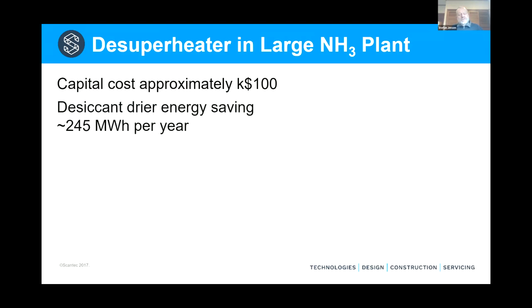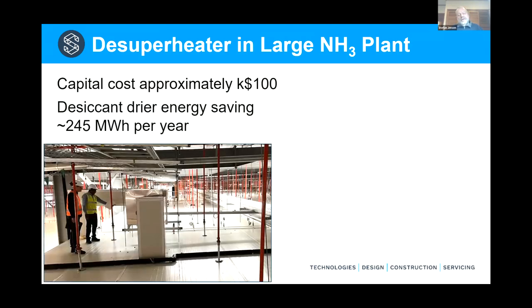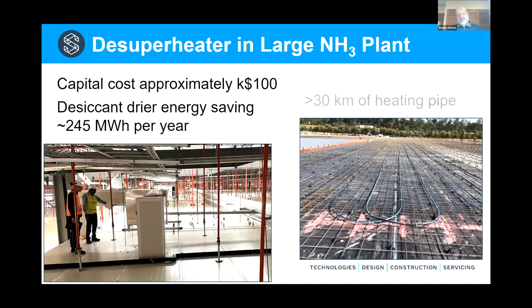So the capital cost of this system I showed you on the other picture is about 100,000. That does not include the storage tank. The insulated 316 stainless steel storage tank for the hot water will add another $70,000. So we are saving 245 megawatt hours a year. If that client pays 10 bucks or 100 bucks per megawatt hour, you can work out it's about $25,000 a year. So a payback of about 4 years. On the picture on the right, you see the subfloor heating pipe being laid. It sits below the structural slab, about 30 kilometers of heating pipe in this particular exercise.